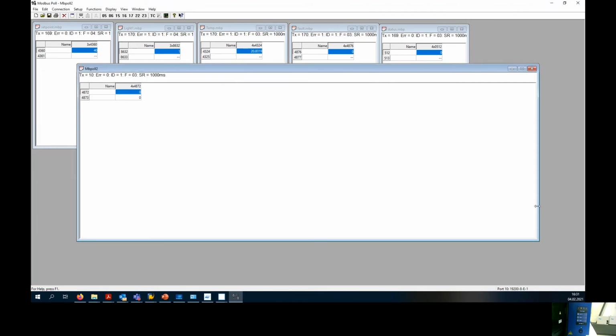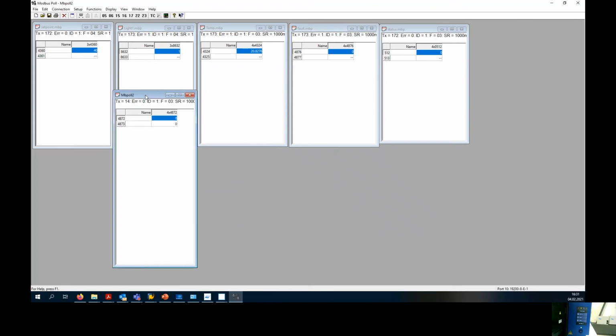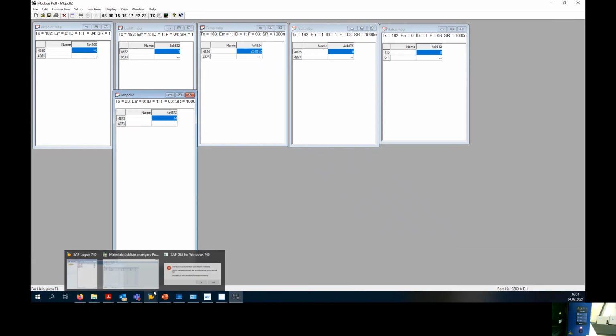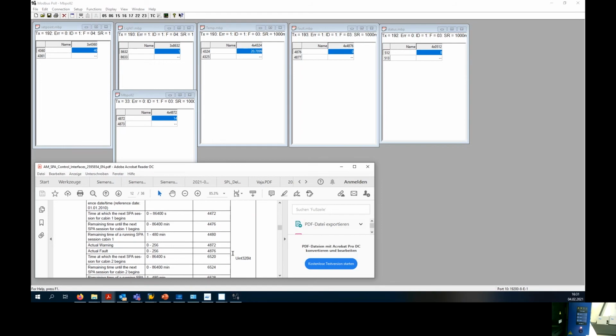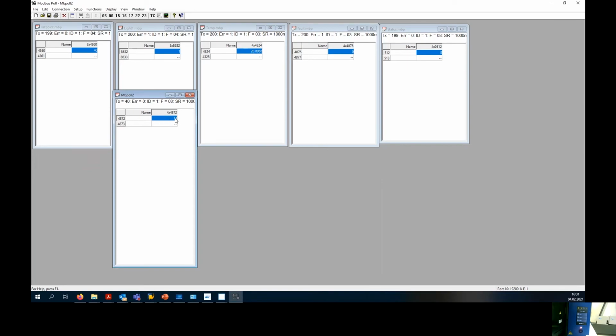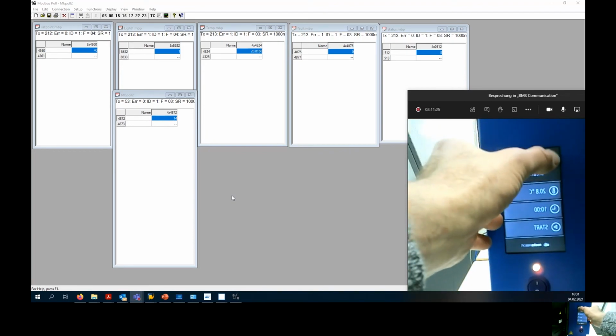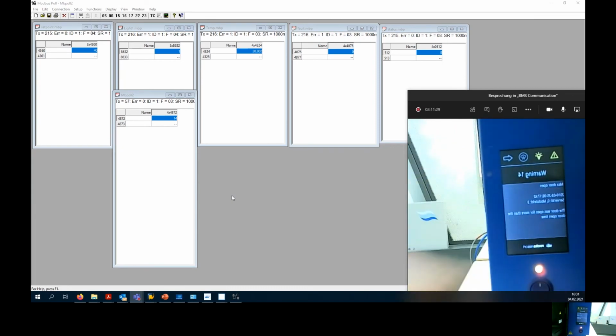So now we're reading the warnings. We need as well format 32-bit unsigned big endian. Format unsigned integer 32-bit. Now it popped up already 14. Let's have a look again on the display. There's a yellow warning triangle. Let's press on the display. And you should see the max door open time. Warning 14, max door open.